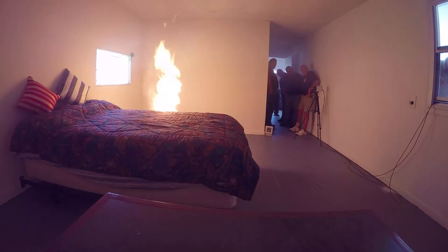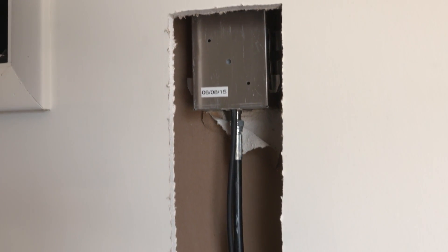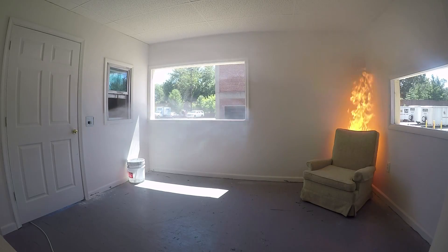We set the system up in each location, had an actual fire, and watched the system perform. The AutoMist system is an easy-to-retrofit water mist system, typically used where it's difficult to retrofit a sprinkler system. It uses much less water and, because of its design, you can plug it in relatively easily — no tank or network of pipes required. You can install it much like a power shower, using a small but powerful pump.